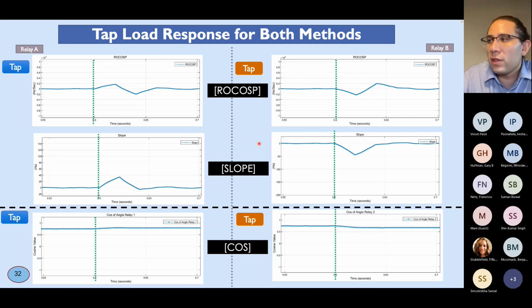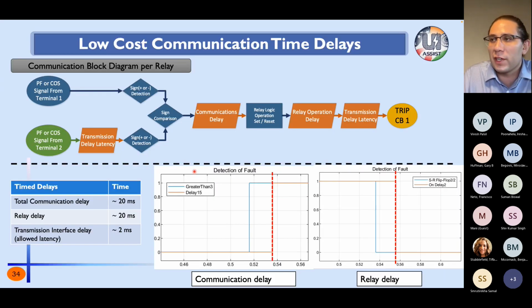For the second method, ROCOSP and the slope of the angle, we can also identify that there is a shift. We can see the response. We can see that it passed the restriction, as I said. But here, the threshold will be 50, which is the grid nominal. So in here, it won't trip, which is okay because it's a tap load. It's not a fault, so it's not necessary to trip. So we can validate that the system operated correctly for different cases.